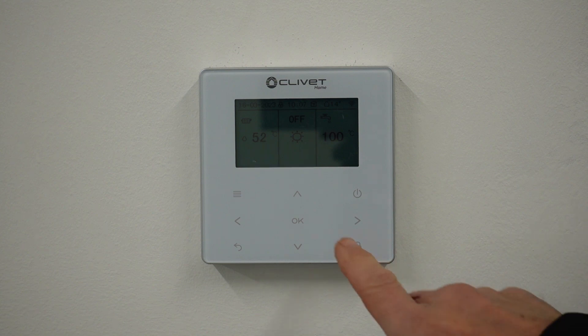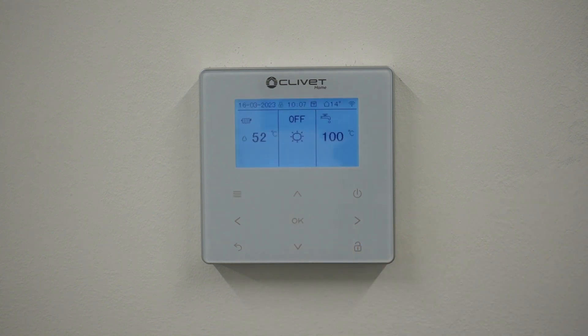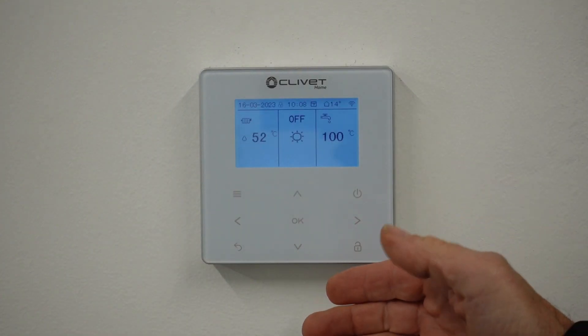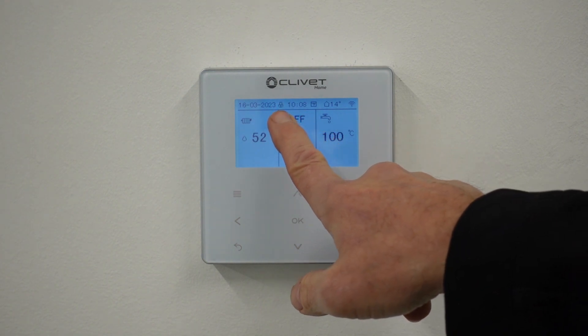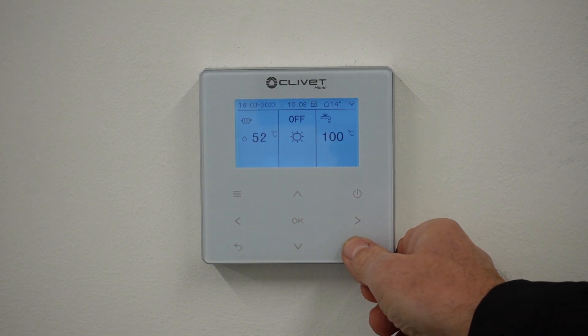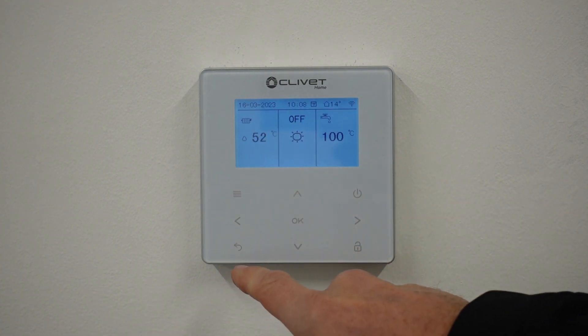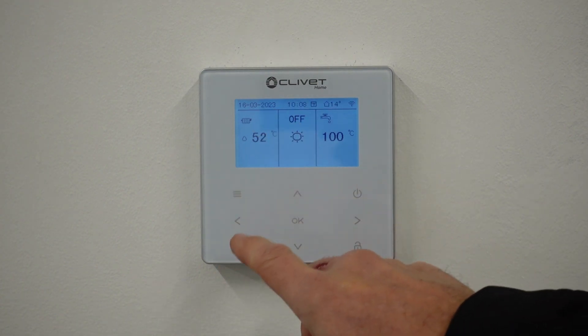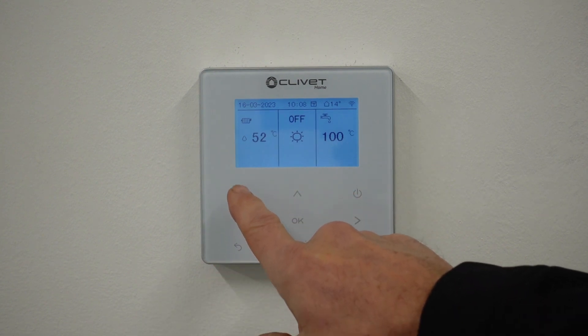Welcome to the ultimate renewables tech channel. This morning I'm going to show you how to set up the weather compensation on a Clivet unit. Currently we have the main screen, which is locked — indicated by the flashing padlock symbol at the top of the screen. To unlock it, just press and hold the padlock for about two seconds, and now it's gone, which means we can enter and start using the buttons and menu options.